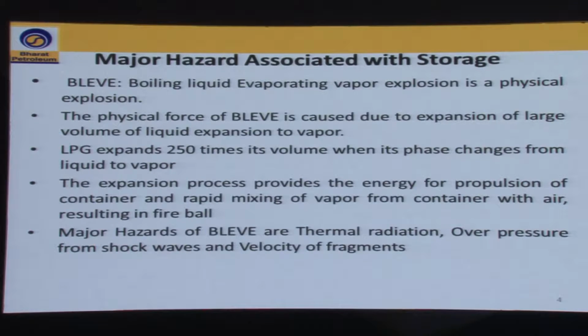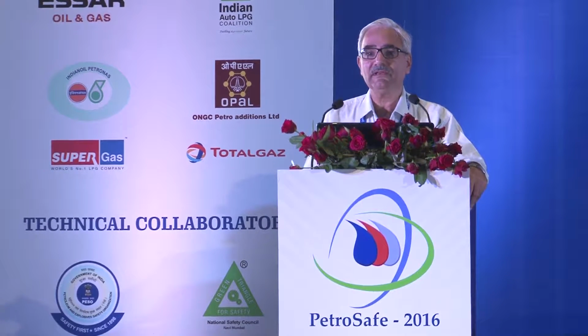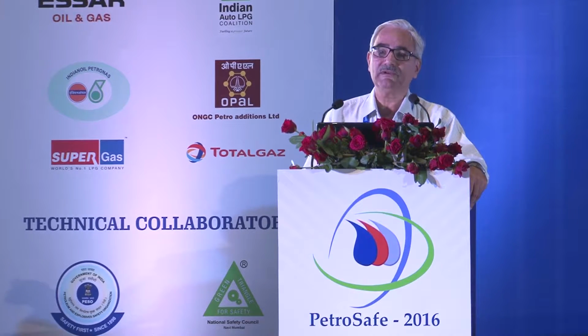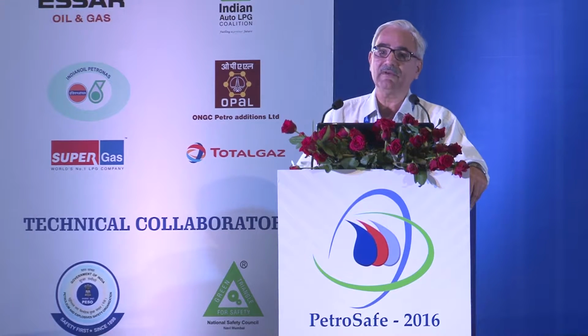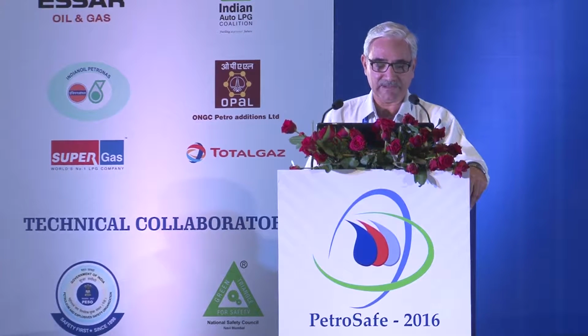The major hazard attached with LPG storage is mainly a BLEVE. In 1984, when the BLEVE incident occurred in Mexico, a need was felt that we have to invent an option for storage of LPG by which we can avoid the BLEVE effect. So then the mounded bullet came up. BLEVE is a boiling liquid expanding vapor explosion, which is a physical explosion. The force is so high when BLEVE occurs. In the Mexico incident, the effect was felt up to 1.2 kilometers from the incident place.